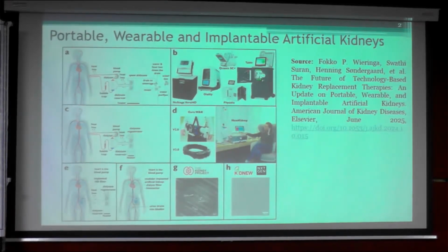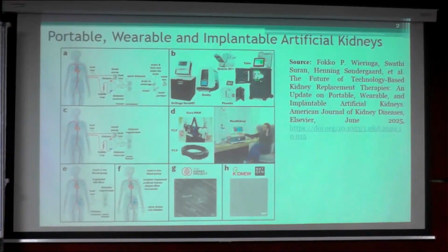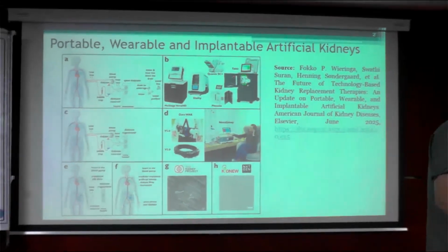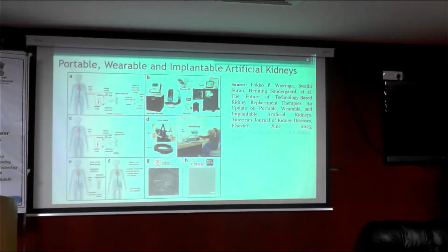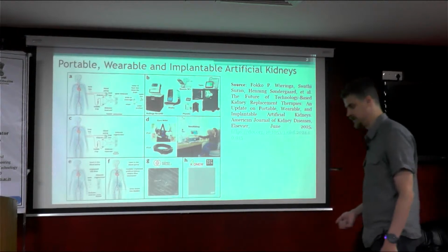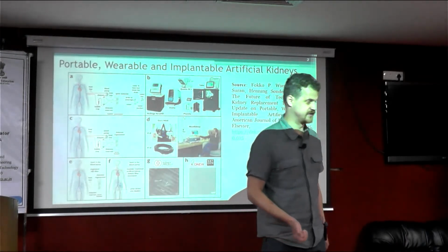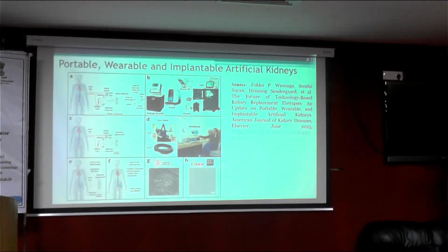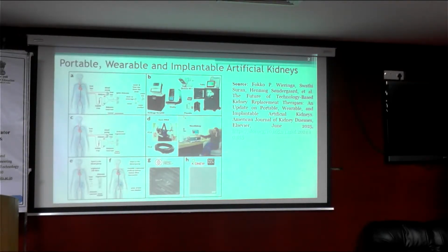Yeah, the primal concern, if we talk about hemodialysis, is actually the water supply. In order to perform a hemodialysis procedure, if we talk about the conventional dialysis methods, it usually goes for 120 to 150 liters per one patient. At the same time, the production of this volume of dialysis fluid requires an even bigger amount of water that has to be specifically prepared for the dialysis for medical purposes.